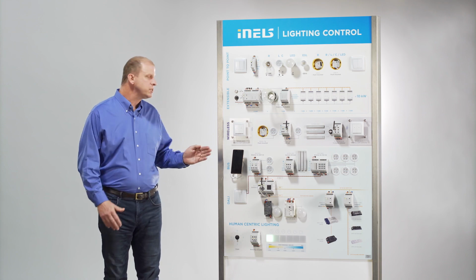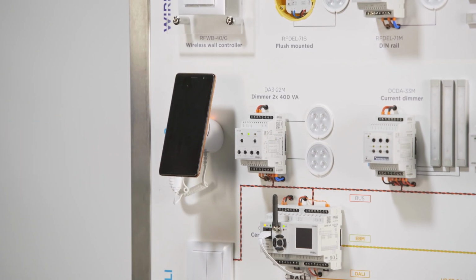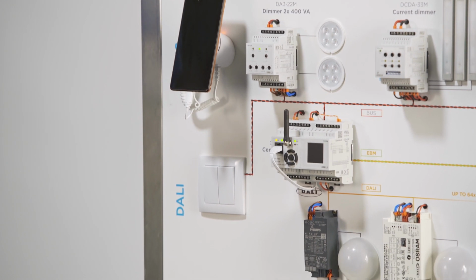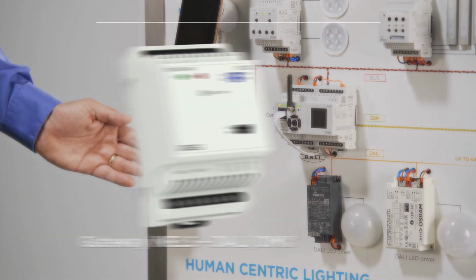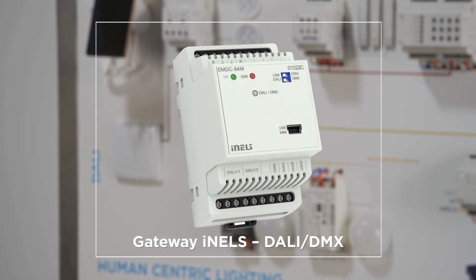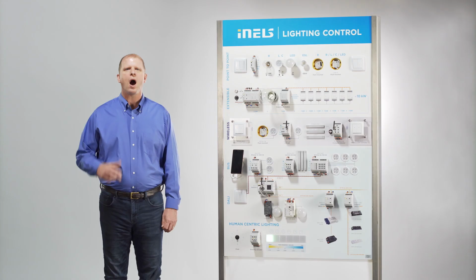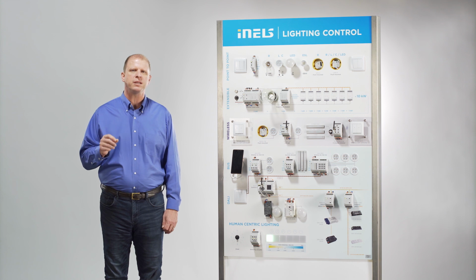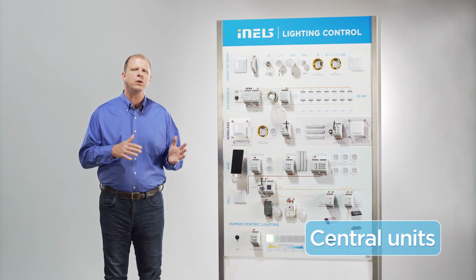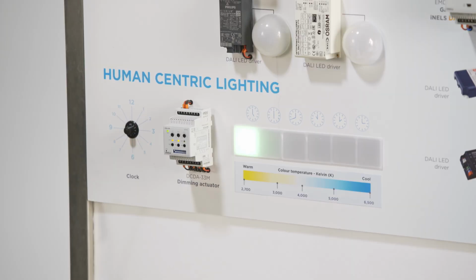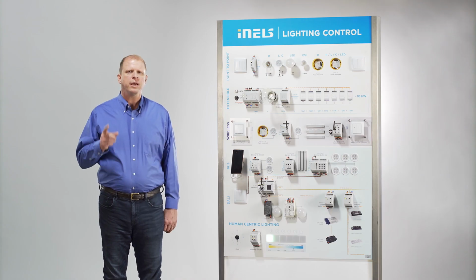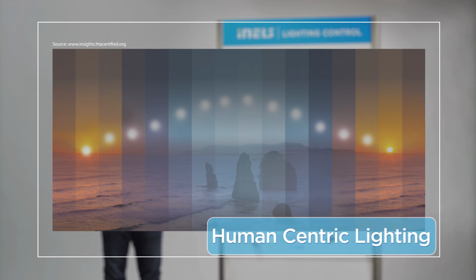It is built on the iNELS bus installation, and its main advantages are a wide range of dimming units, DALI and DMX bus support, and advanced configuration and programming options. All commands and communication are processed by the central unit communicating with the dimmer or DALI DMX converter. Thanks to advanced features such as an astronomical module, conditional configuration, timers, and counters, it is possible to create a lighting control concept based on mixing the white temperature according to the phase of the day and the surrounding natural light.